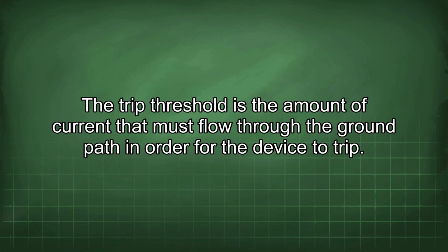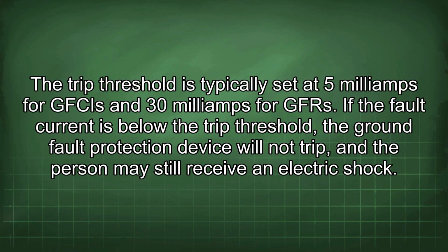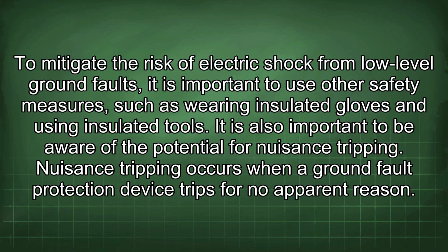The trip threshold is the amount of current that must flow through the ground path in order for the device to trip. The trip threshold is typically set at 5 mA for GFCIs and 30 mA for GFR. If the fault current is below the trip threshold, the ground fault protection device will not trip, and the person may still receive an electric shock. To mitigate the risk of electric shock from low-level ground faults, it is important to use other safety measures, such as wearing insulated gloves and using insulated tools.